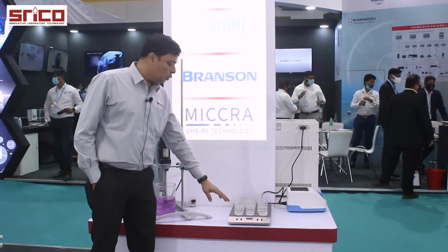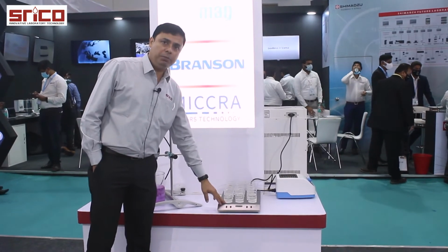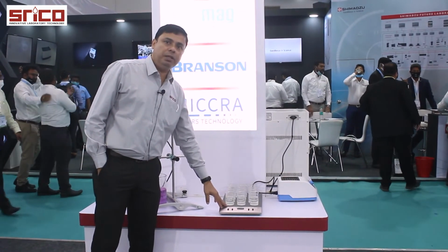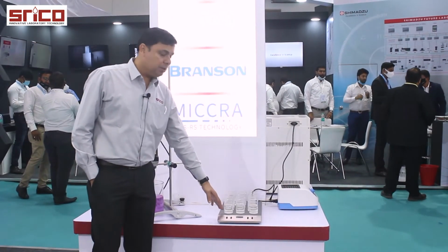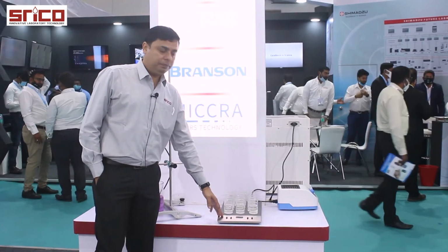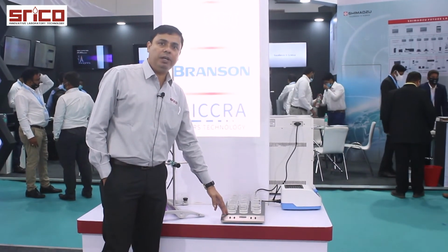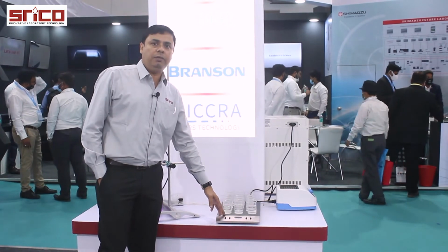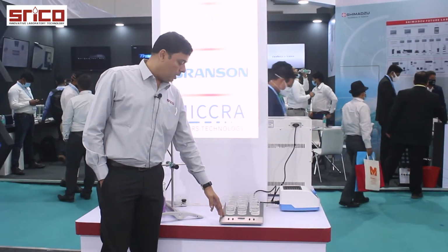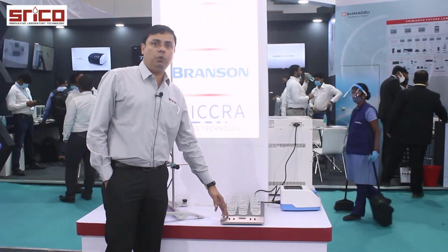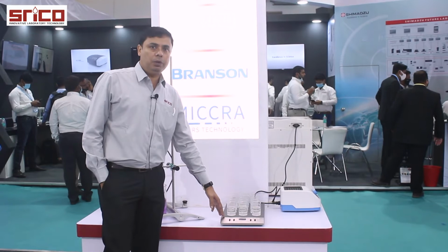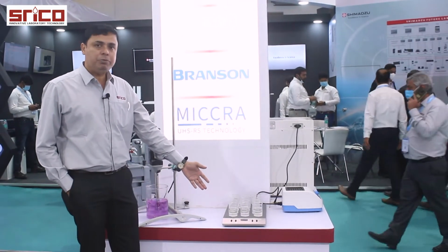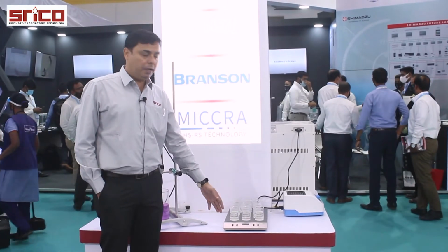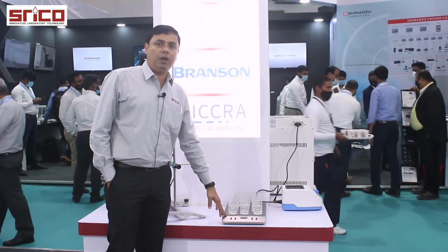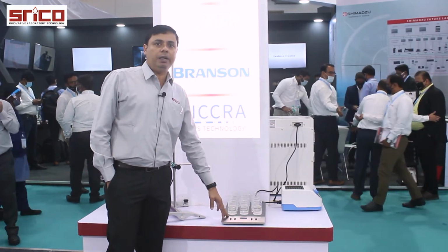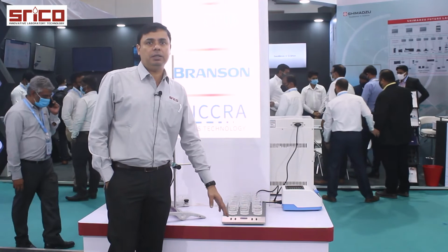This is again another good magnetic stirrer from 2Mag, Germany. And the beauty of this machine is we can have the controller separately. That means the drive unit separate and the controller separate. And we can immerse this drive unit inside a water bath. That means the drive unit is waterproof, submersible type, and we can handle volume up to 1000 liter starting from 100 ml onwards. And we have multi-points like this, 15 points, even 60 points, 90 points like this. And this company is also giving a dry bath stirrer. That means hot plate with magnetic stirrer, multi-points with separate controller.